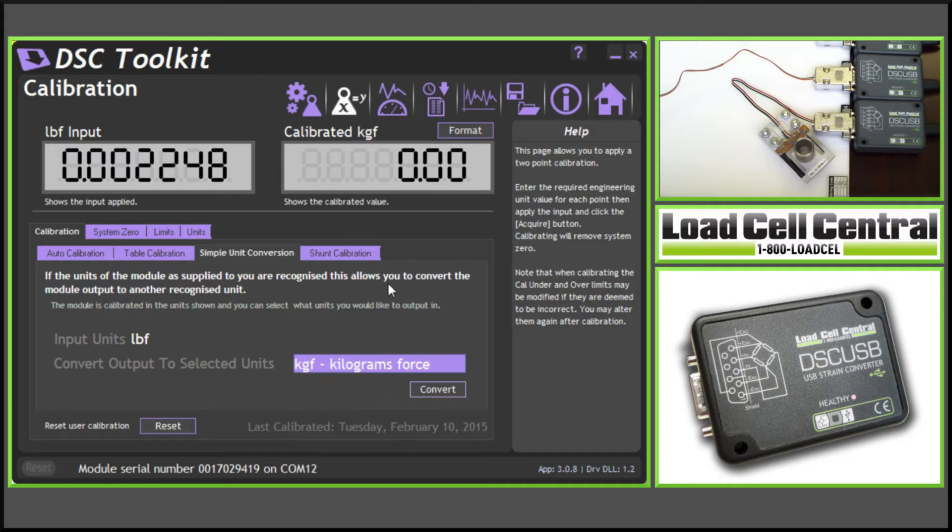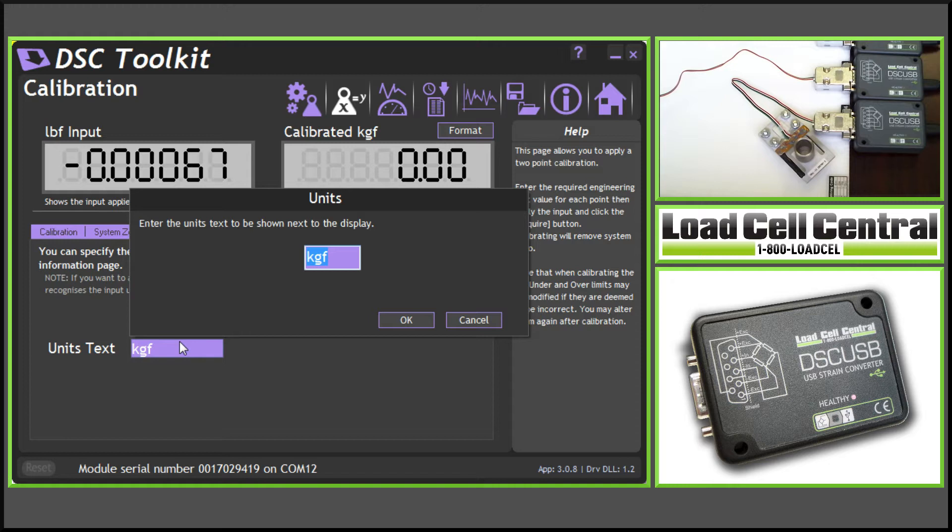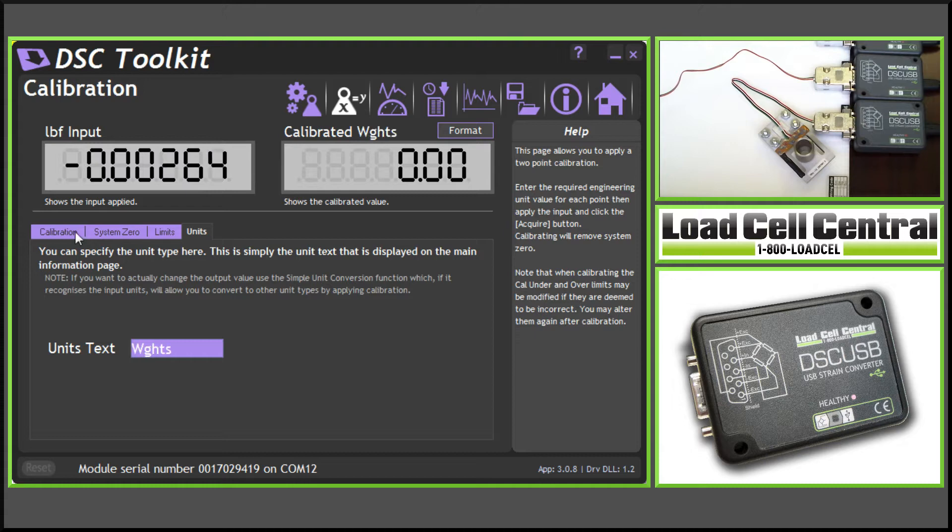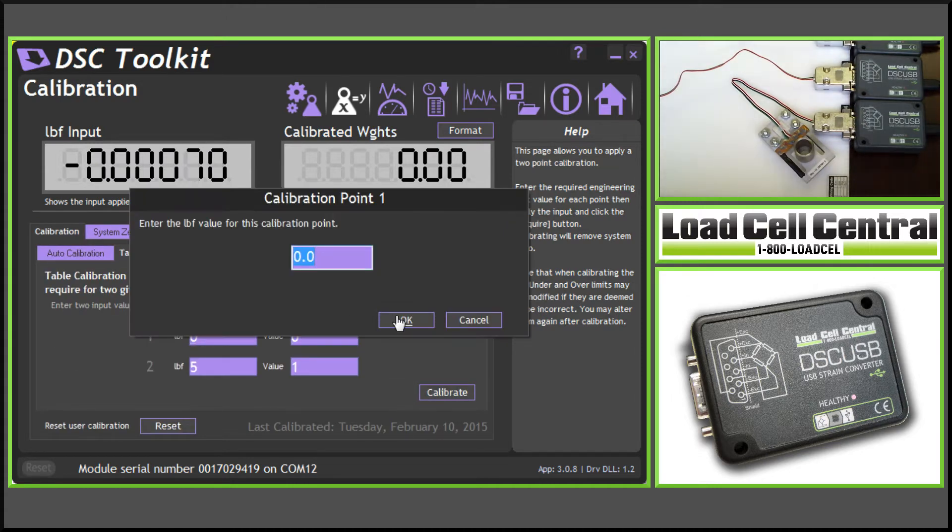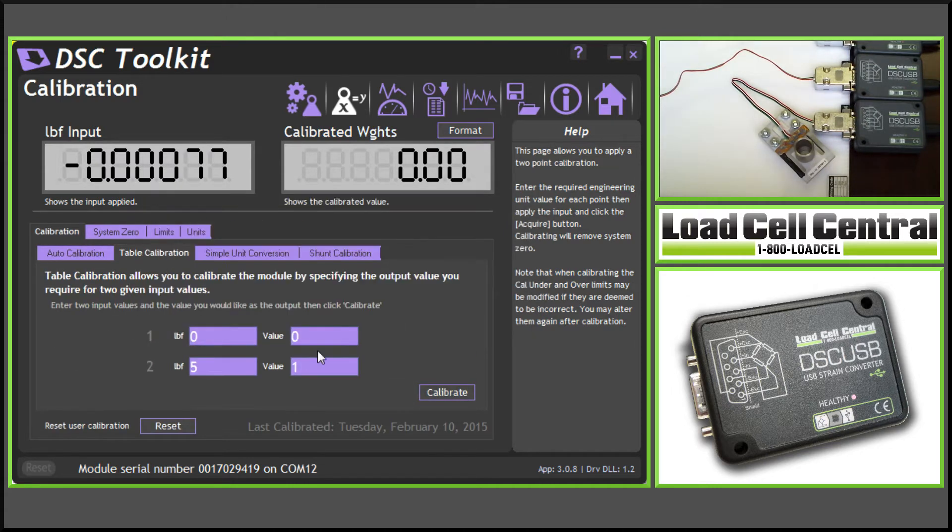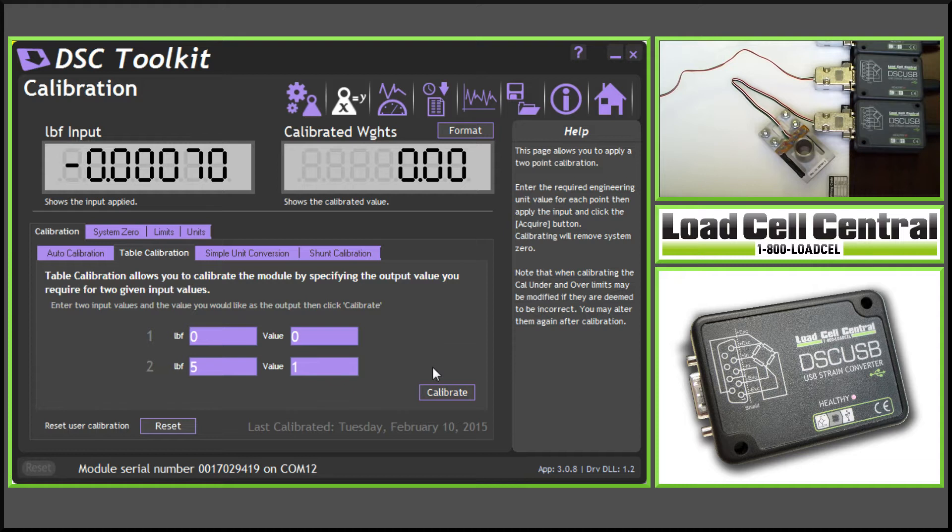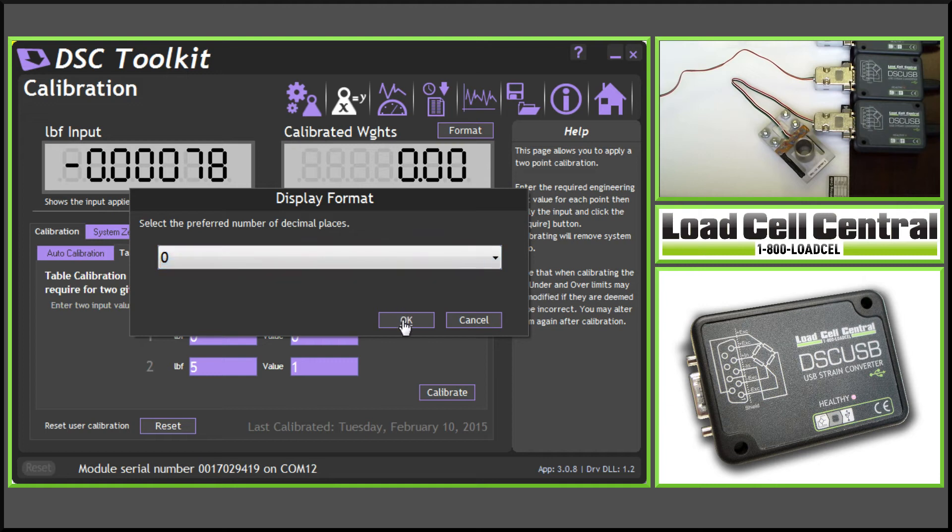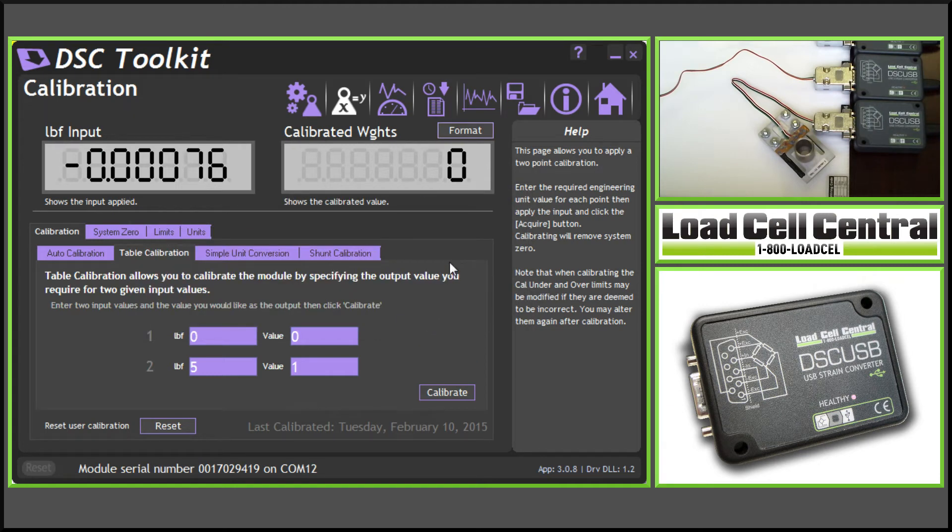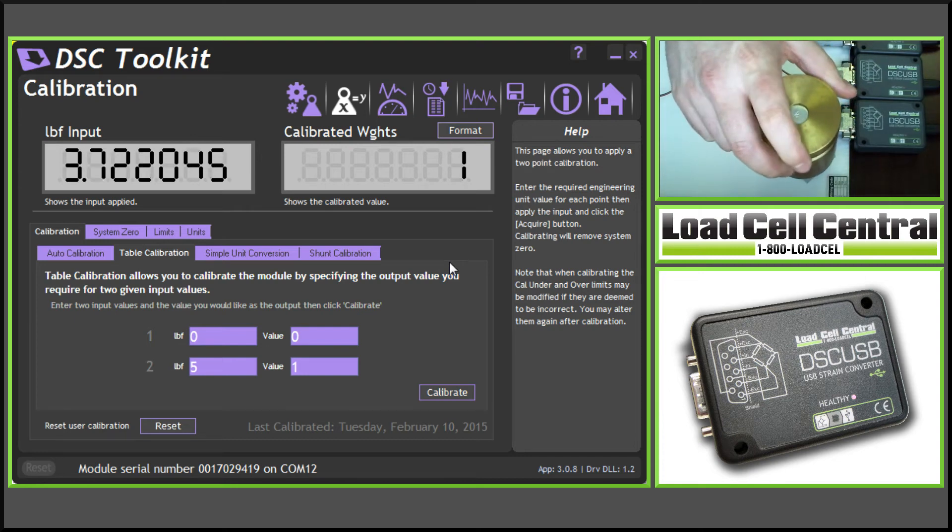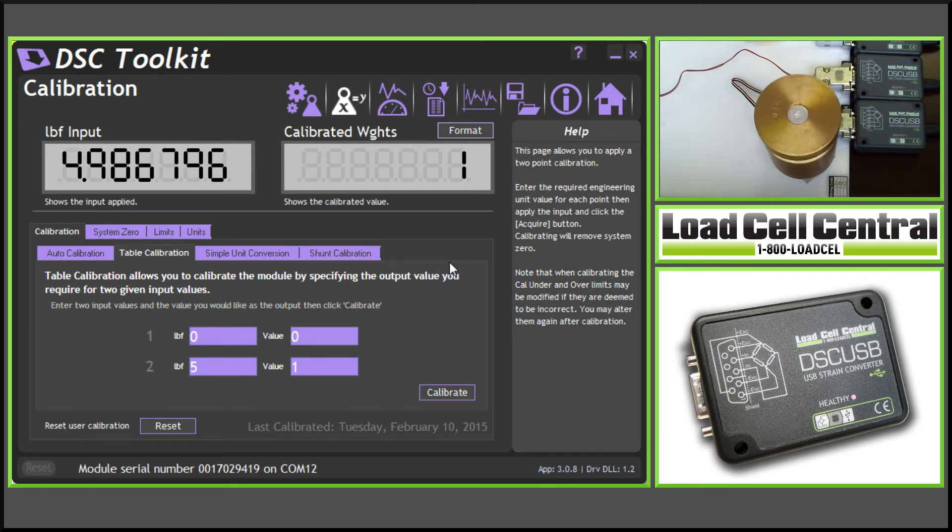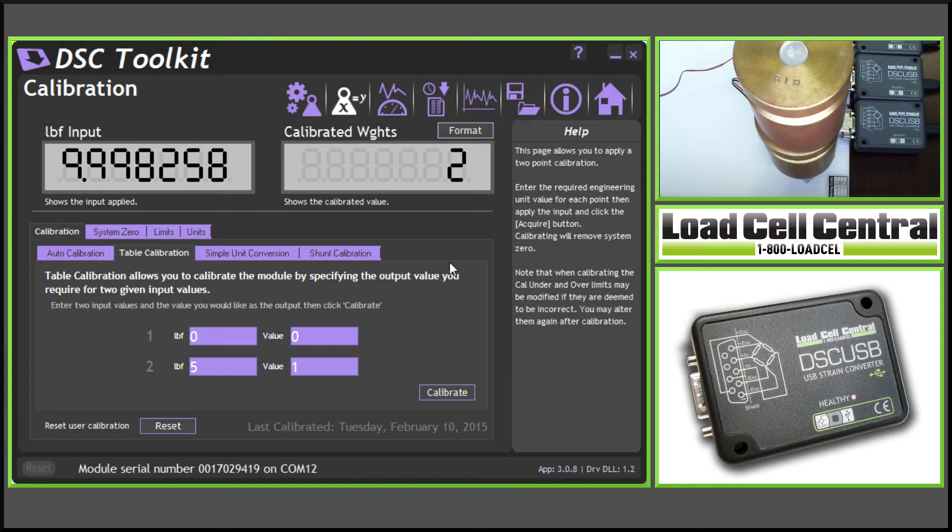Also available in this screen is a custom unit section where we can specify any unit we'd like. We could do something like parts counting, so I'm going to go ahead and use weights, and then perform a table calibration, stating that 0 pounds equals 0 weights, and 5 pounds equals 1 weight. Calibrate. Now, if I format this to whole numbers, we'll be able to see that when I add 1 weight, it'll tell me that I have 1 weight. We could do this with anything like jugs, tubs, bags, things like that. We could also do something like this with gallons.